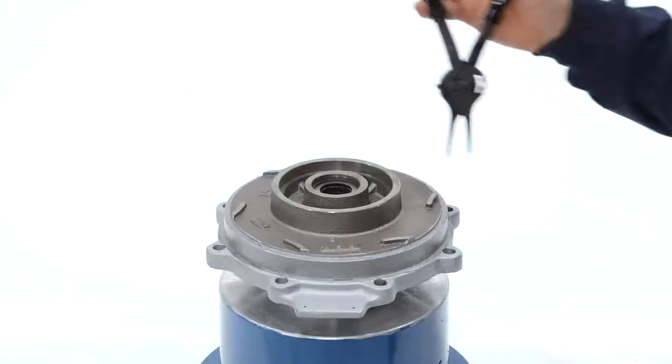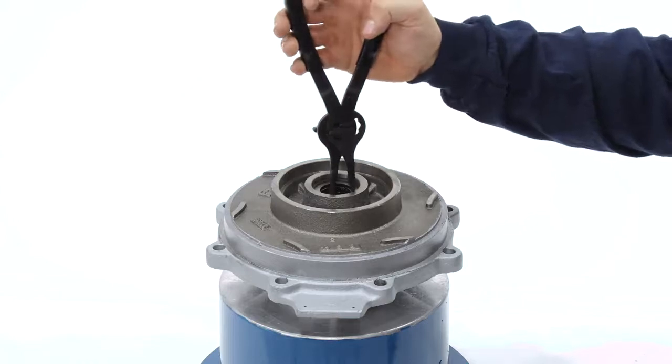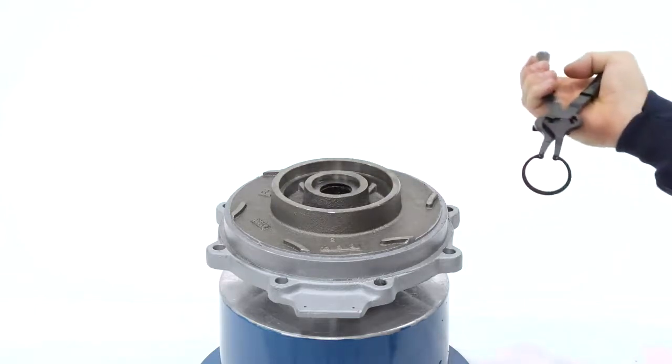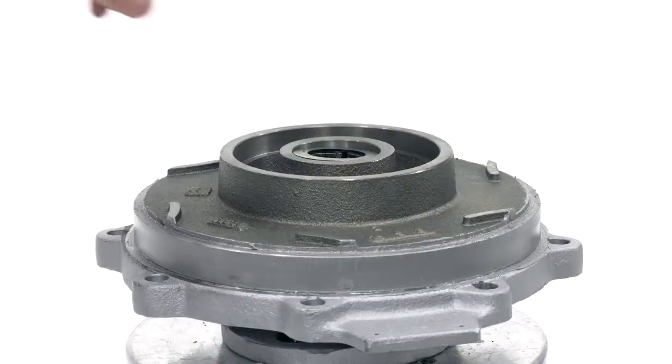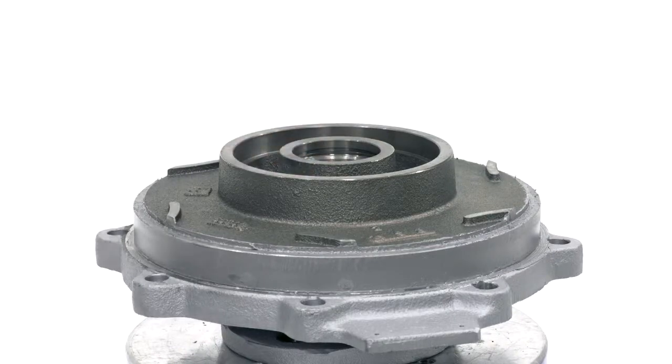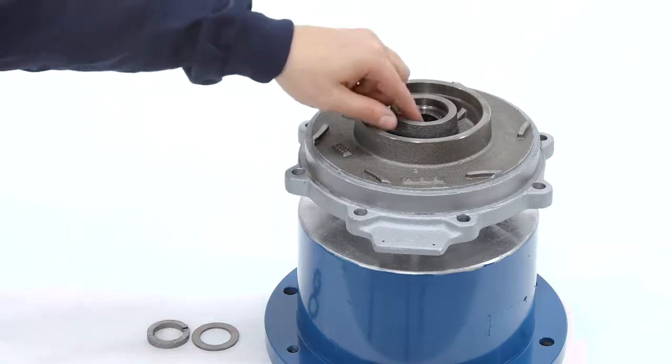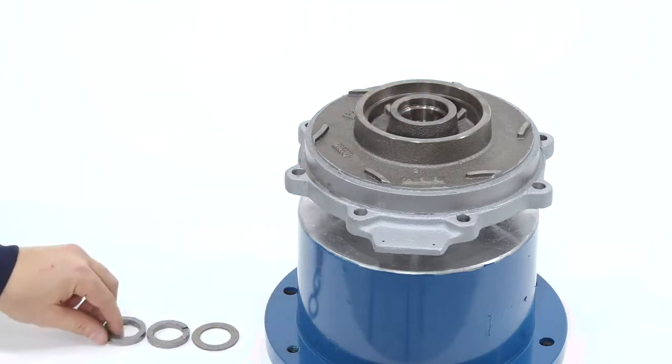Flip the casing cover over on the stand. Use a pair of snap ring pliers to remove the snap ring from the center of the stuffing box. Remove the spacer, followed by the packing. The casing cover is now fully disassembled.